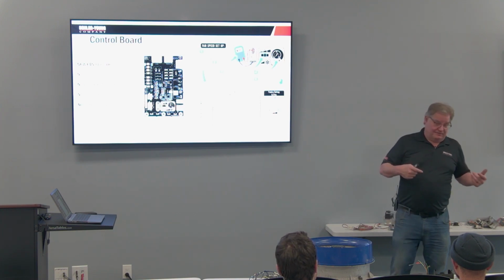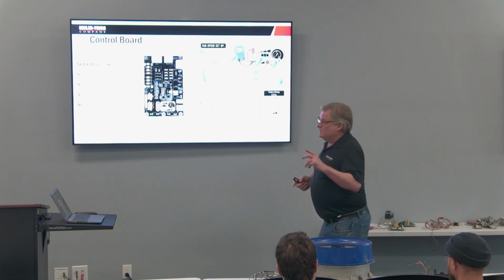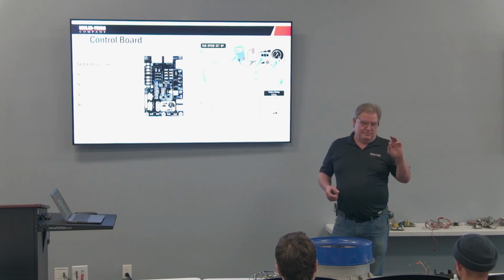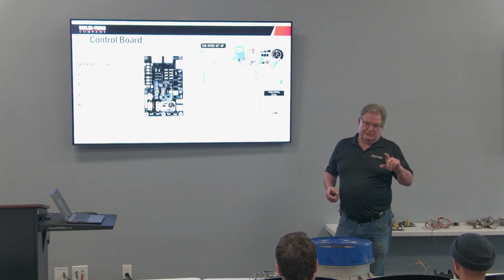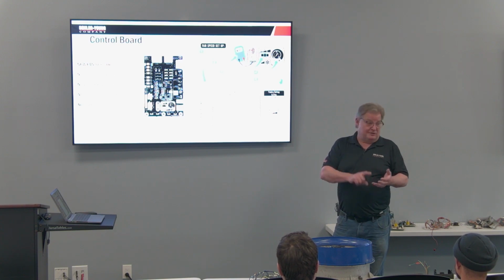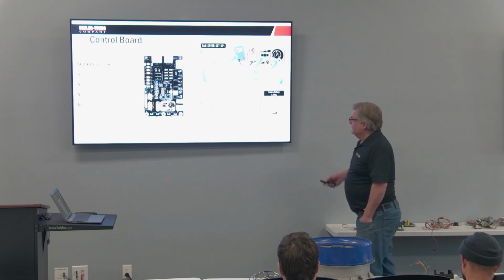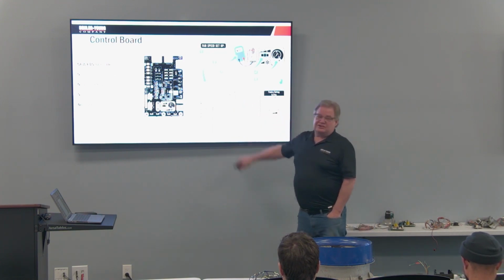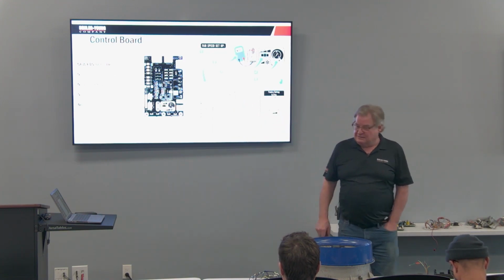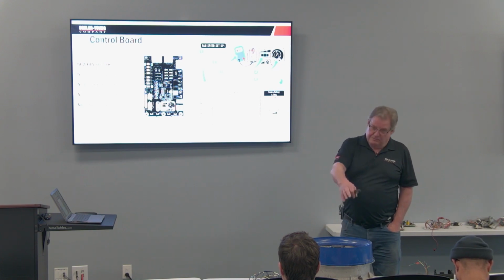We didn't have these when I first started, but that should be one of your second or third meters you buy, a manometer. Okay. We use it for gas pressure. We're going to use it for static pressure on duct systems. We're going to use it for pressure switches. So it's got pretty many uses. So we're going to use our manometer to check the static. We're not going to guess, okay, because we're going to end up with blower motor problems.